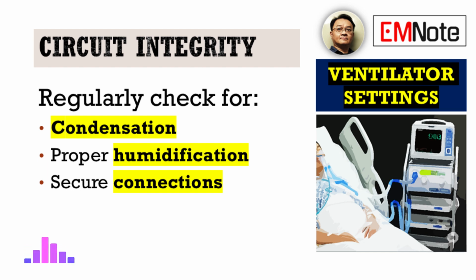Proactive checks looking for condensation, ensuring humidity, checking connections, combined with an immediate and systematic response to alarms are fundamental for continuous patient safety. These steps ensure that the ventilation system functions optimally and provides uninterrupted support. Every component, every connection, every single breath truly matters for the patient's well-being.